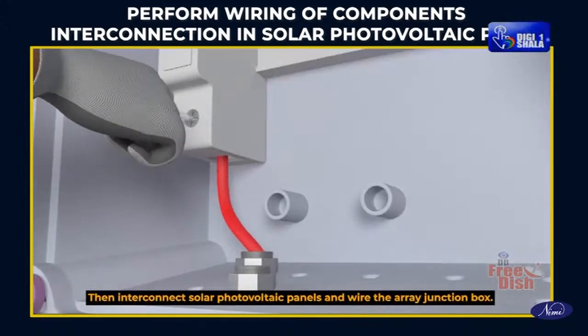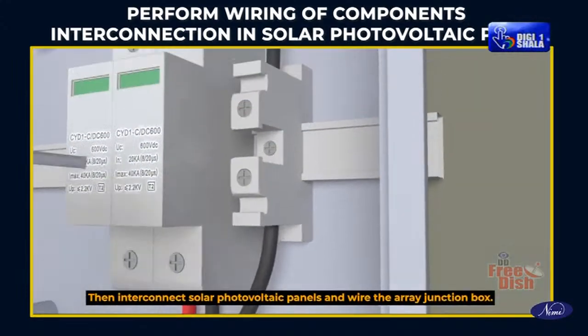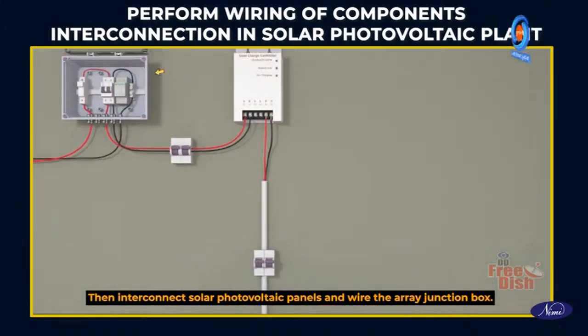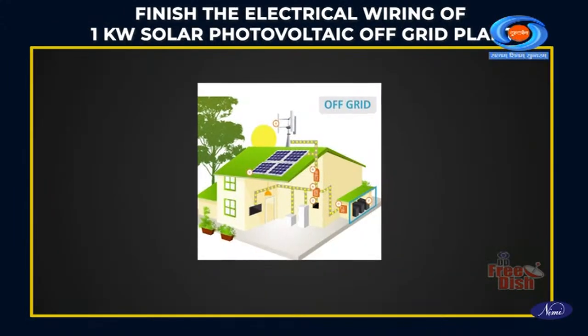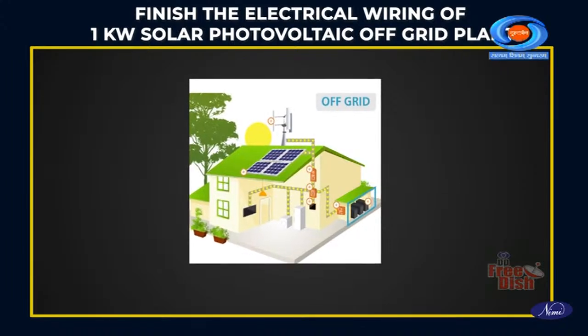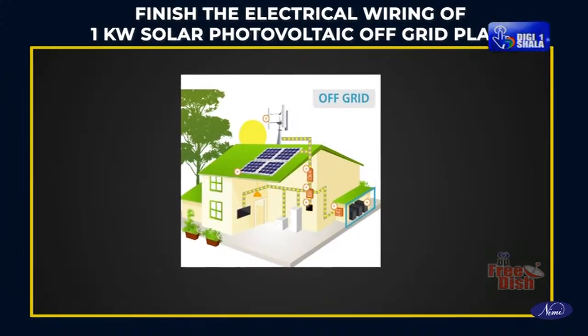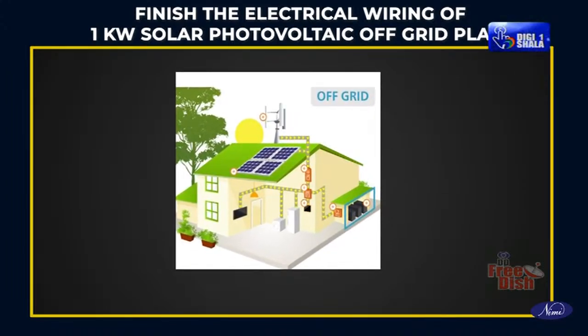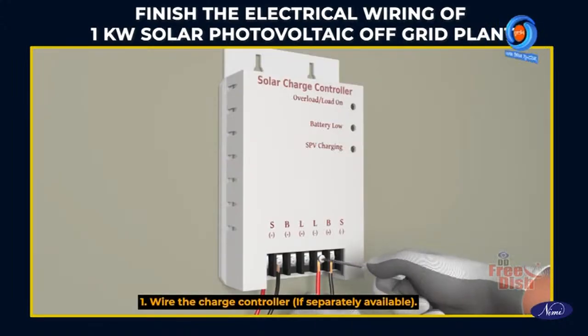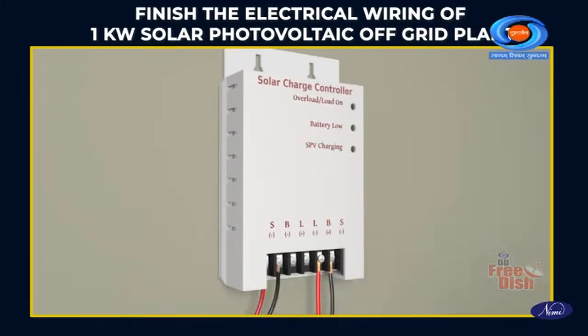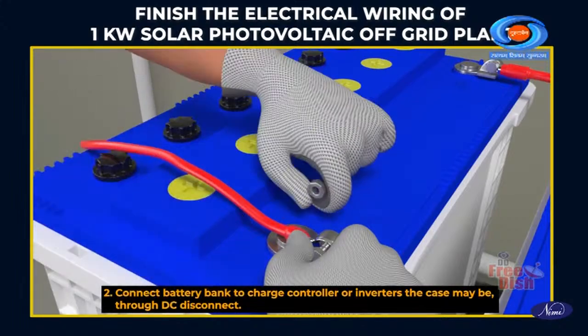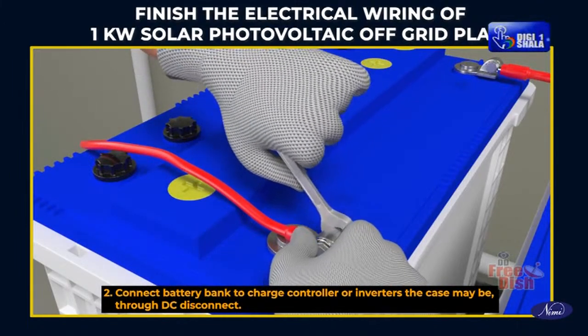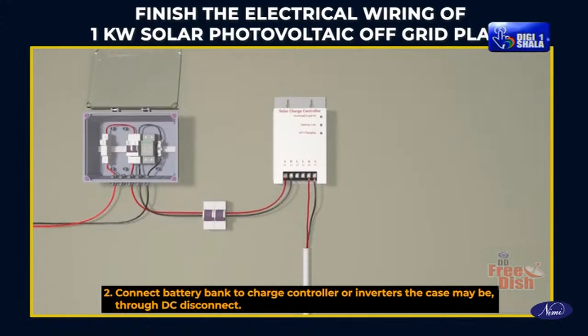Then interconnect solar photovoltaic panels and wire the array junction box. Finish the electrical wiring of the 1 kilowatt solar photovoltaic off-grid plant. Wire the charge controller if separately available. Connect the battery bank to the charge controller or inverters, as the case may be, through DC disconnect.